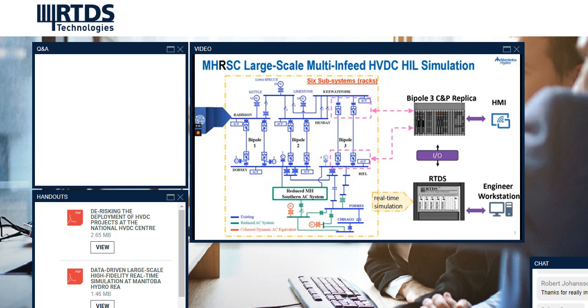This model includes a highly granular and faithful representation of northern generating stations with synchronous machines, a frequency-dependent AC transmission network, HVDC Bipole 1 and 2 controls derived from the original analog circuit board analysis done about 40 years ago, reduced southern AC network representation, HVDC synchronous condensers with exciters, interconnections to the pertinent U.S. power system, and two coherency-based AC dynamic equivalents representing the two prominent inter-area modes, together with the special protection schemes, remedial action schemes, and conventional protection schemes as well.